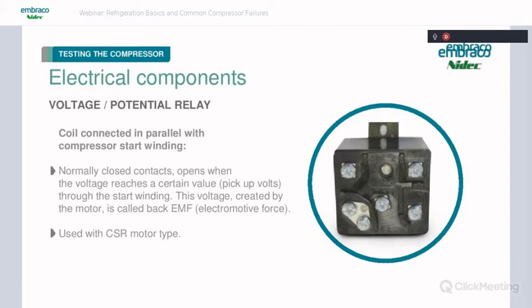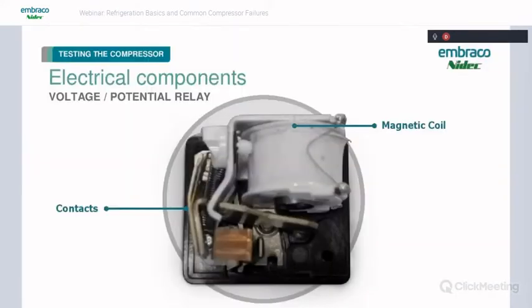We see these on the CSR motor types, the larger compressors, because it's got that advantage of having normally closed contacts, so there's less potential for arcing at startup. So this is a look inside that relay. You can see that magnetic coil that senses the back EMF. When it gets enough back EMF to this coil, you can see it pulls this armature in, opening these contacts and de-energizing the start winding.